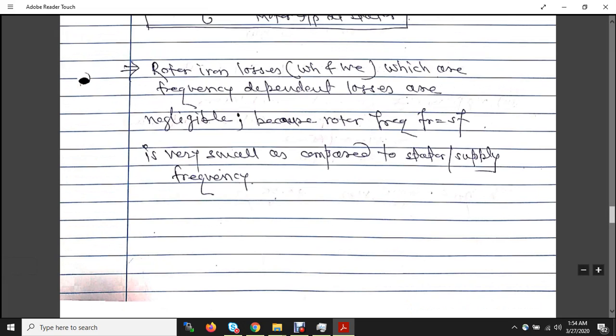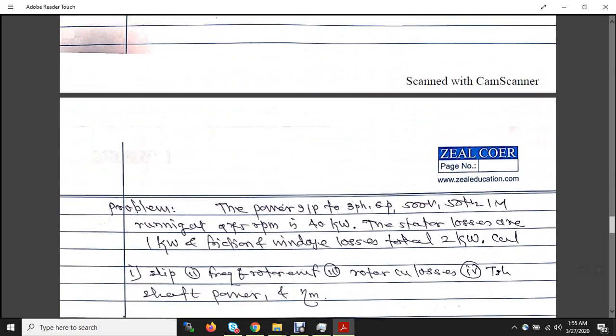So in this video, we have learned the family of torque slip characteristics, that is in three regions. First region is at light load, where the relation is linear. When R2 equal to SX2, the torque becomes maximum, and later on when the load is further increased, the slip increases, and therefore the term SX2 becomes greater than R2, and therefore the torque is inversely proportional to slip, and it becomes a rectangular hyperbola. And finally at slip S equal to 1, that is at standstill, we will get the starting torque.